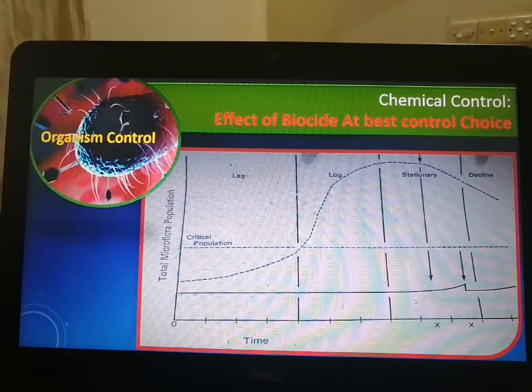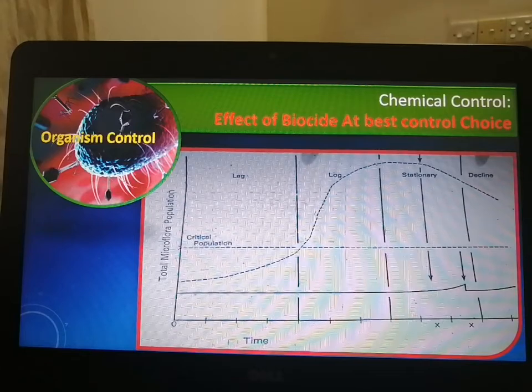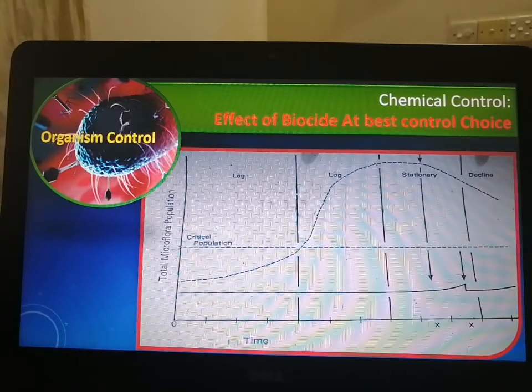Usually for a system we might not monitor the biological count, and that creates a problem: we don't know how much biocide we are dosing, we don't know where we are standing, we don't know whether the biocide is correct or not. There is no testing or monitoring of the application, activity or performance of the biocide, and that creates problems for the system. Even if we dose oxidizing biocide, we don't have any opportunity to test its activity. Is it functional or not functional? Is it effective or not effective? These are the major challenges for a country like Bangladesh, for customers like us and suppliers like many of us. We can't have control, measurement and monitoring, and that keeps us in the dark.